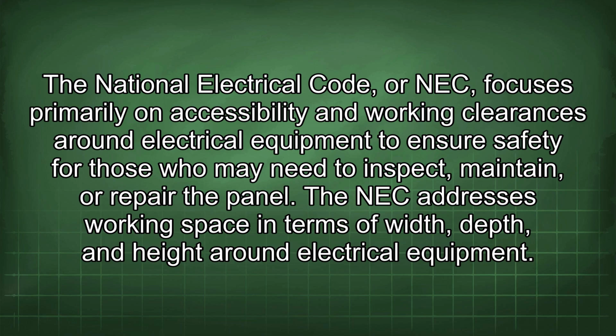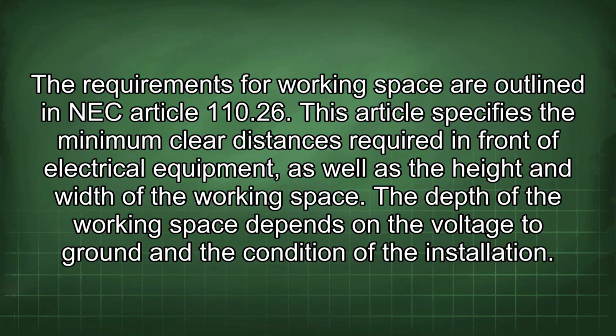The NEC addresses working space in terms of width, depth, and height around electrical equipment. The requirements for working space are outlined in NEC Article 110.26. This article specifies the minimum clear distances required in front of electrical equipment, as well as the height and width of the working space. The depth of the working space depends on the voltage to ground and the condition of the installation.